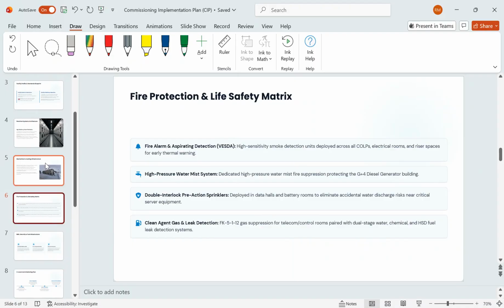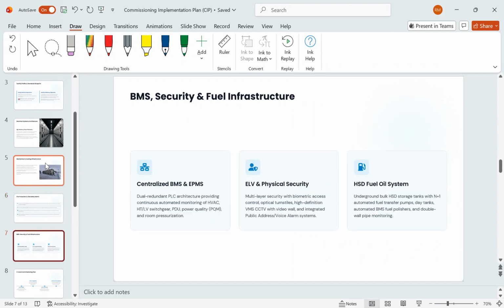Again, coming to fire protection and life safety, it has a fire alarm system, and VESDA systems deployed across all the data halls, electrical rooms, and riser spaces for thermal warnings. A high pressure water mist system is installed at DG sets, and a double interlock pre-action system is employed at data halls and battery rooms, with clean agent and leak detection systems. It has BMS and security fuel architecture: centralized BMS and EPMS system, ELV and physical security system, and HSD fuel oil system with N plus 1.